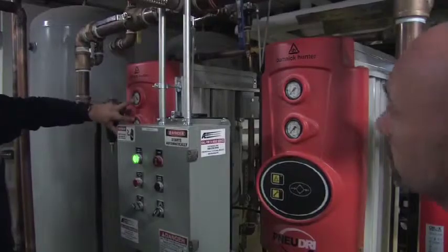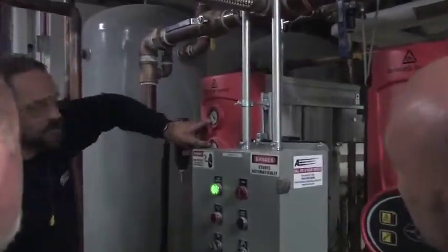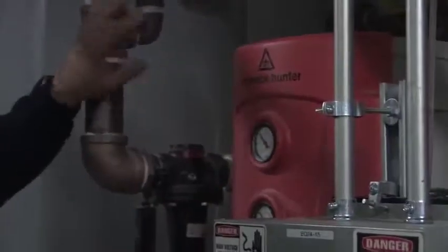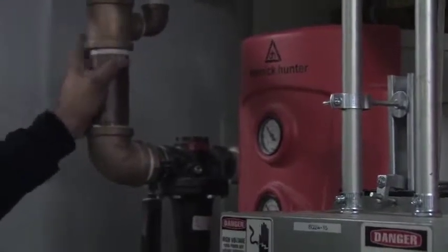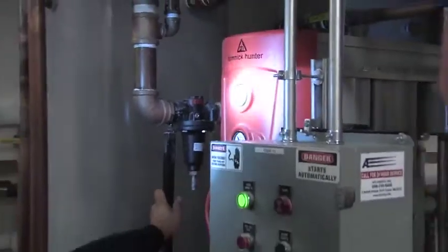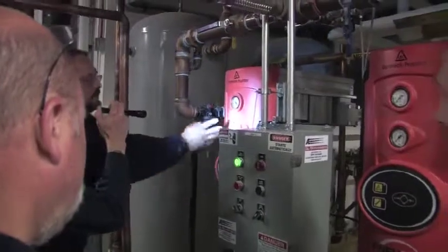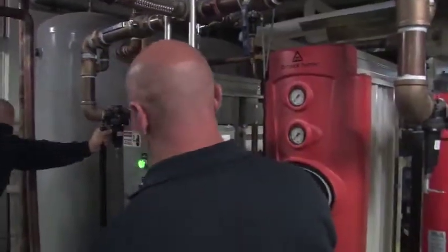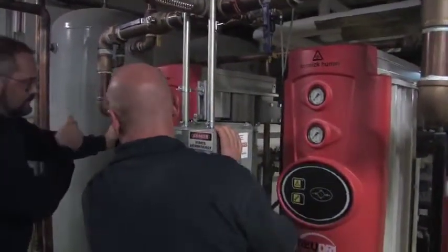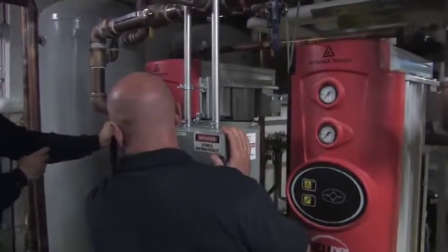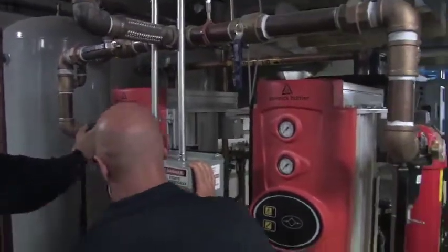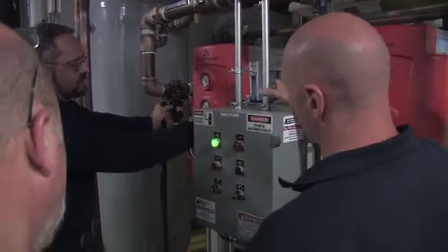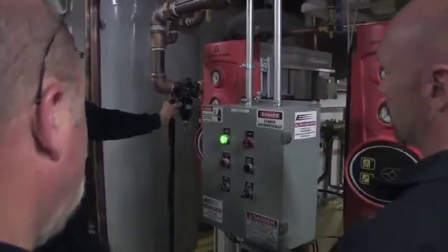So right now, both towers are pressurized. The purge is suspended because of our dew point. Did you mean both banks? I'm not trying to be a stickler for terminology, but I don't want to get confused. Both banks, because this tower is pressurized, bank right and left of these 2 gauges. This one's your left, this is the right. So both of them are pressurized.